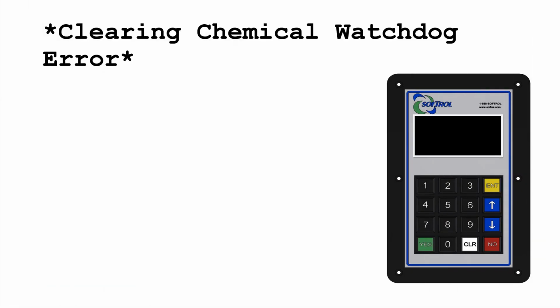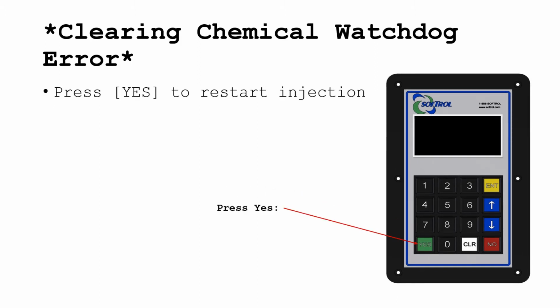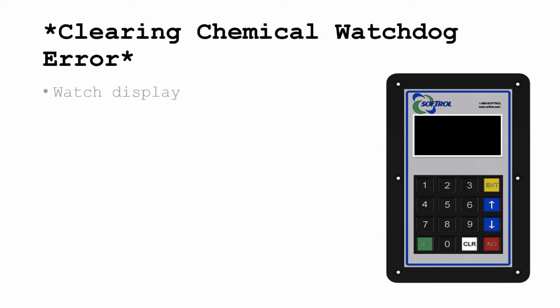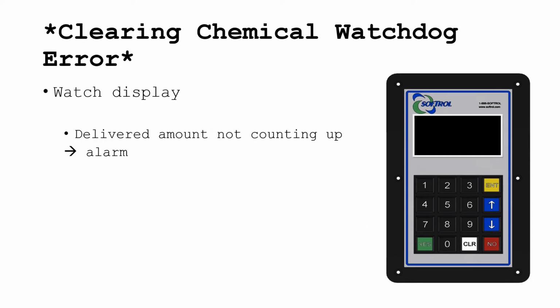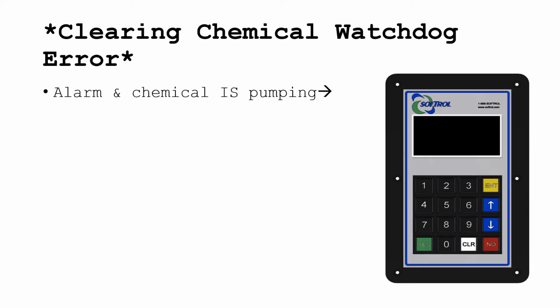If the alarm is due to a hardware issue, press the CLR key to silence the alarm. Enter the level 7 password to clear the alarm from the screen. Press the yes key to restart the injection. Watch the display. If the delivered amount is not counting up, the system will alarm again. If the system alarms and chemical is pumping, the flow meter most likely needs to be cleared.